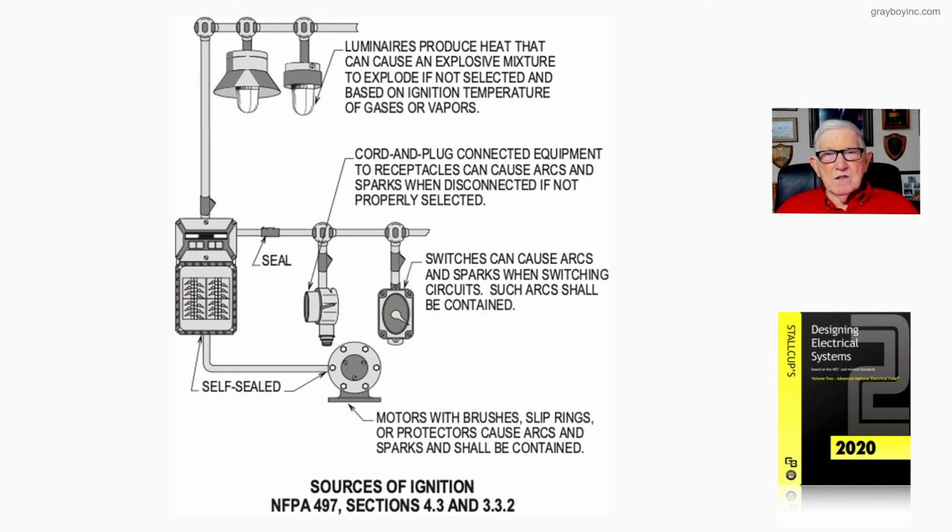To deal with hazardous locations, you just have to have the NEC, NFPA 497, NFPA 499, NFPA 496, and when you deal with ventilation, NFPA 30. So those are some standards that we should have on hand if we deal with hazardous locations. And this illustration is just pointing out that the equipment must be selected so that sources of ignition are totally enclosed in such a manner that they're not a threat with their arc or spark to cause an explosion in a hazardous classified area.